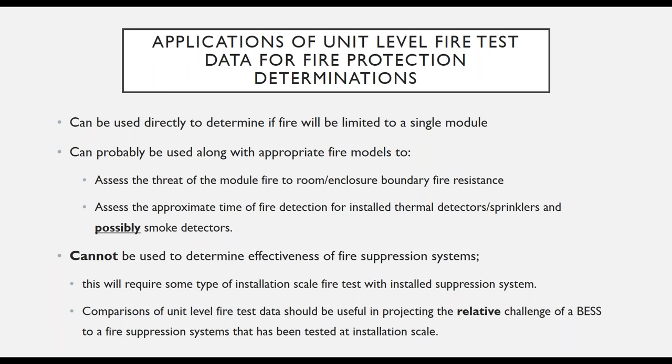It probably can be used along with appropriate fire models, fire protection engineering models, to assess the threat of the module fire to the room and the enclosure boundary fire resistance, to assess the approximate time of fire detection for installed thermal detectors, such as fusible link sprinkler heads, and possibly for smoke detectors.